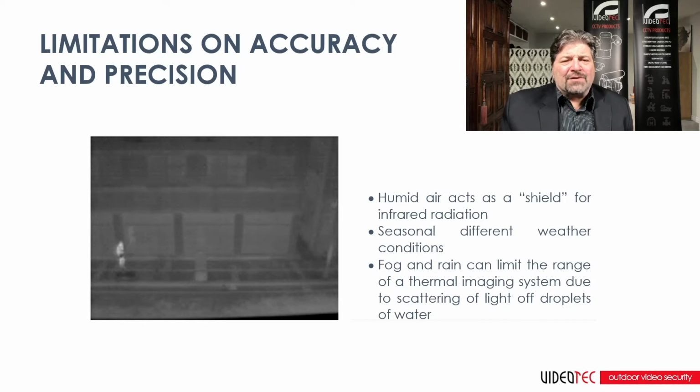Although there are many factors that may influence the accuracy of radiometric surface temperature measurements, the atmospheric transmission factors can be largely negated by making measurements within 10 meters or less of the target surface in cool and clear atmospheric settings. These conditions mitigate the impact of air temperature, relative humidity, and air particulates. For longer distances, the atmospheric conditions, camera distance, humidity, and temperature will need to be well characterized to calculate the atmospheric transmission.